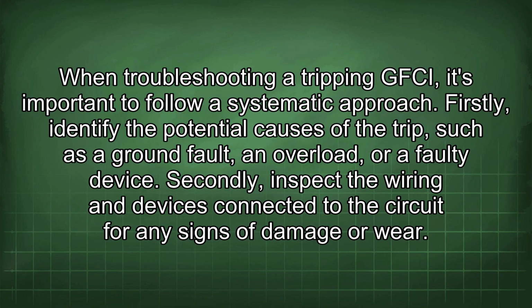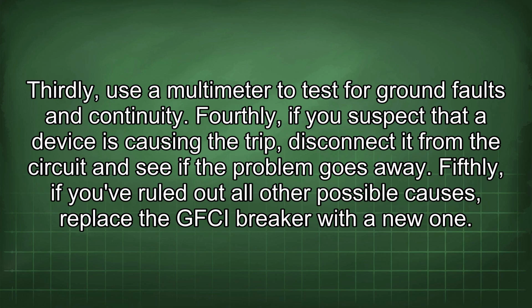When troubleshooting a tripping GFCI, it's important to follow a systematic approach. Firstly, identify the potential causes of the trip, such as a ground fault, an overload, or a faulty device. Secondly, inspect the wiring and devices connected to the circuit for any signs of damage or wear. Thirdly, use a multimeter to test for ground faults and continuity.